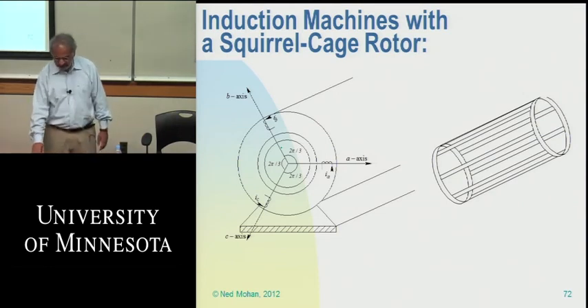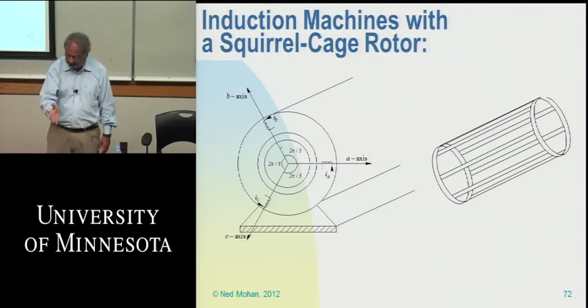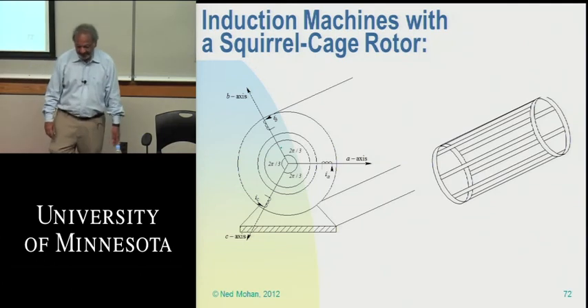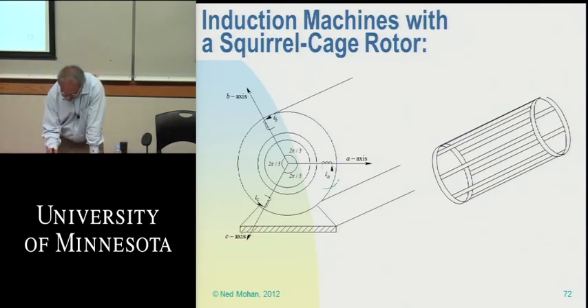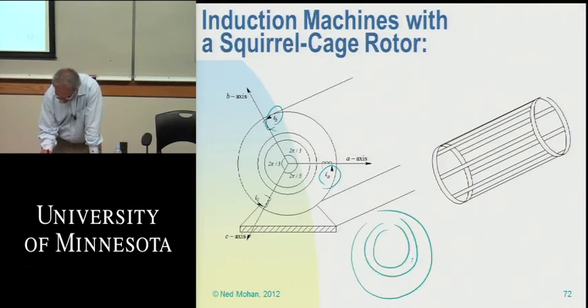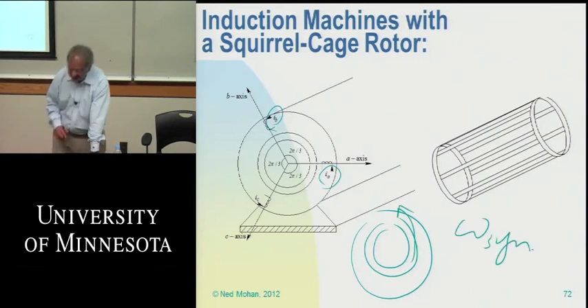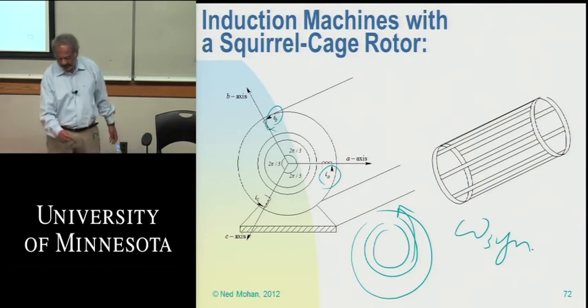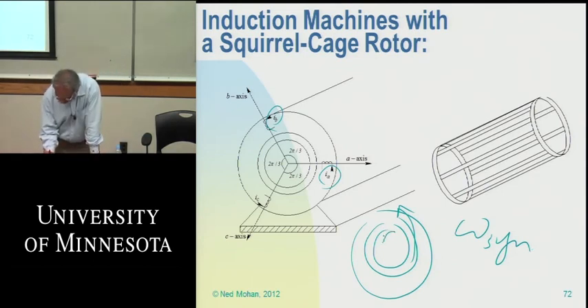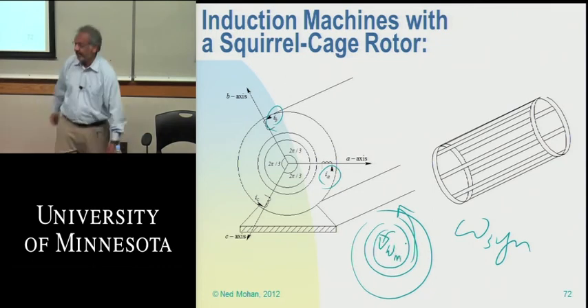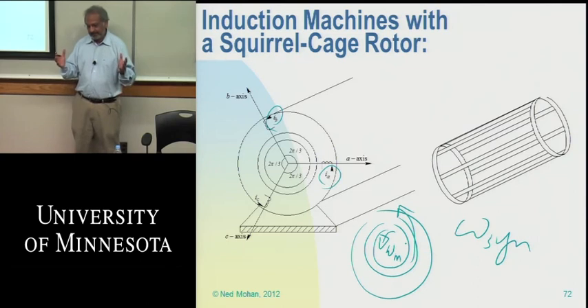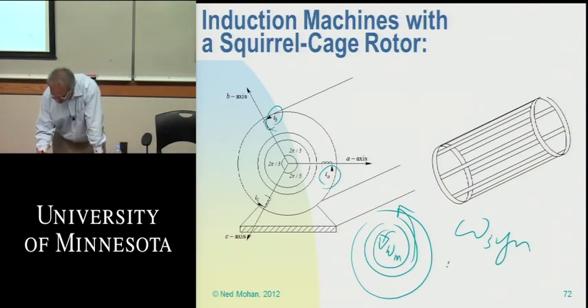So how does this work? The bottom line, without going into a lot of details here in 2 minutes, is that when you supply voltages and currents to these three windings, the magnetic field here is rotating in the air gap at the synchronous speed, related to the frequency at which you are supplying these currents IA and IB and IC. But the rotor itself is turning at a speed omega m, which is different. Okay? That means there is a slip between the two. We call it slip speed, right? So this slip speed is defined as omega sync minus omega sub m.